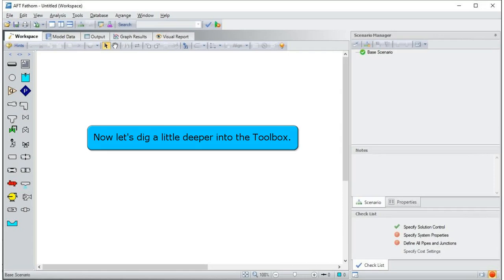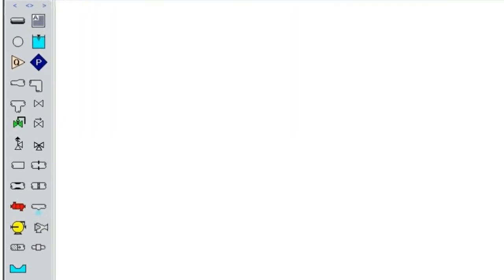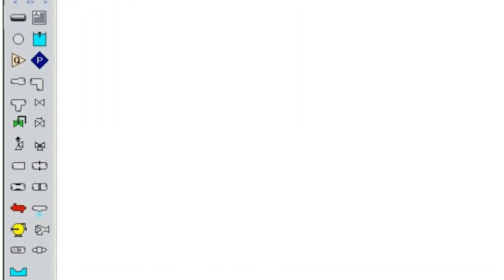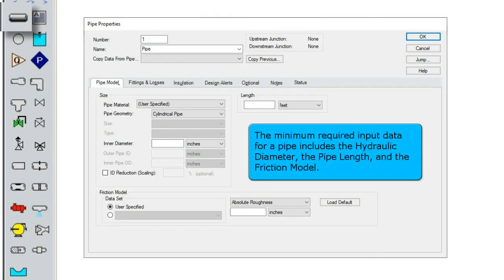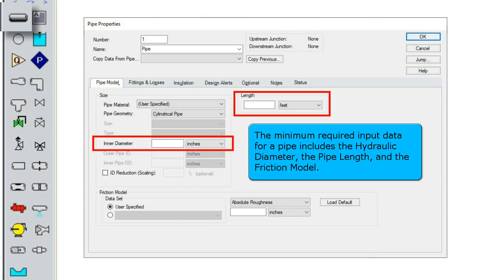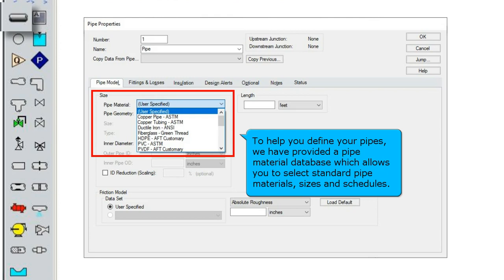Now let's dig a little deeper into the toolbox. The pipe drawing tool allows you to draw pipes on your workspace. Keep in mind that every pipe must be connected to a junction at either end. The minimum required input data for a pipe includes the hydraulic diameter, the pipe length, and the friction model.